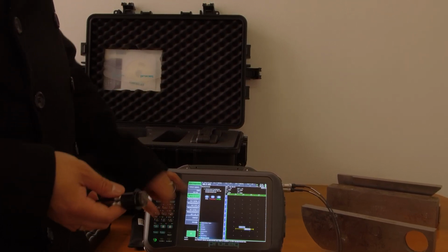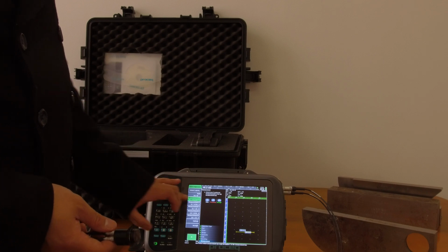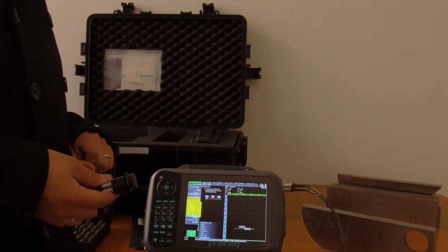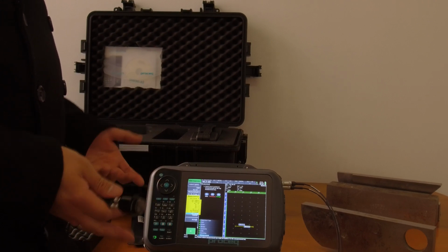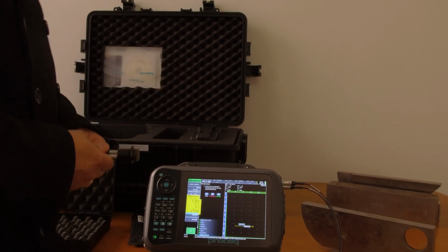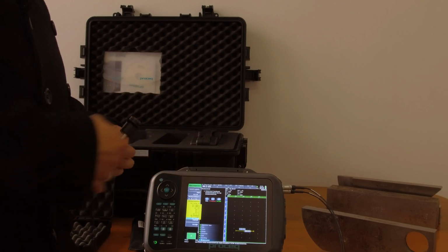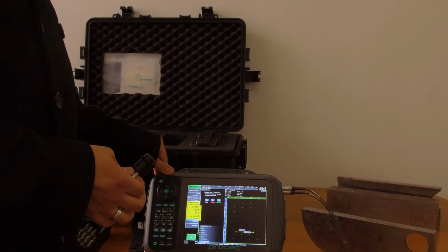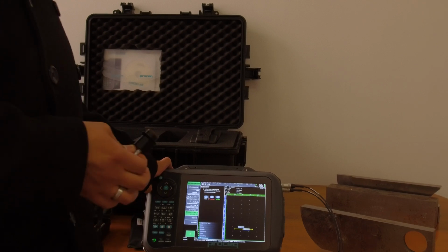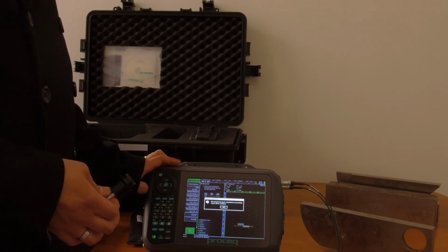These options here represent these options up here. So the first one that I've got for measurement 1 is your mono pulse echo gain. Okay, I can then change it to all sorts of things relating to AWS, relating to DACs, relating to full percentage of full screen heights. I can put in my projection distance for an angle probe. I can put in my estimated depth. I can put in my actual time base, or how long the sound has actually taken to get there. So we'll just leave it at this point, but you do have lots of options to set this up just how you want to set it up. So at this point, I'm just going to accept.